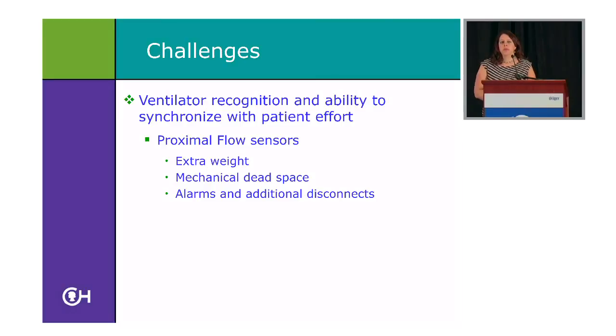And you know, my prior unit, we used one of those machines. We did the test between the two. And the tidal volume, if you did all of your circuit calibrations and everything with a warm, wet circuit, and did your calculations over, then it actually was pretty close, their proximal flow sensor to their distal flow sensor. However, when you had little preemies and 1 ml of tidal volume makes a big difference, then 1 ml of tidal volume you need to have and you need to be able to measure. So for preemies, unfortunately, you really need to have that proximal flow sensor.